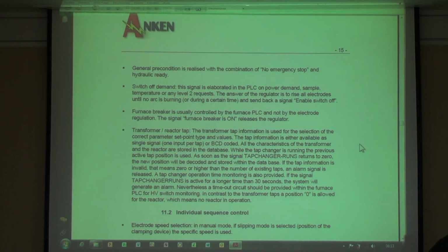타임아웃 서킷은 타임 카운터로 1, 2, 3 재는 겁니다. 20까지로 세팅했다면 20이 딱 되면 이벤트가 발생했다는 시그널이 접점 출력이 되는 거지. 그게 HV 스위치 모니터링 시스템으로 가든지 해서, 그 알람 이벤트에 대해 적절한 대응을 하기 위한 시퀀스가 되는 겁니다. 그러니까 30초가 지나가면 탭 체인저 시그널에 관련된 워닝 신호가 뜨는 것과는 별도로, HV 스위치 모니터링을 위한 PLC 시그널로서 타임아웃 서킷을 계속 제공해야 된다는 말이에요. 이건 좀 더 디테일해야 되는데.